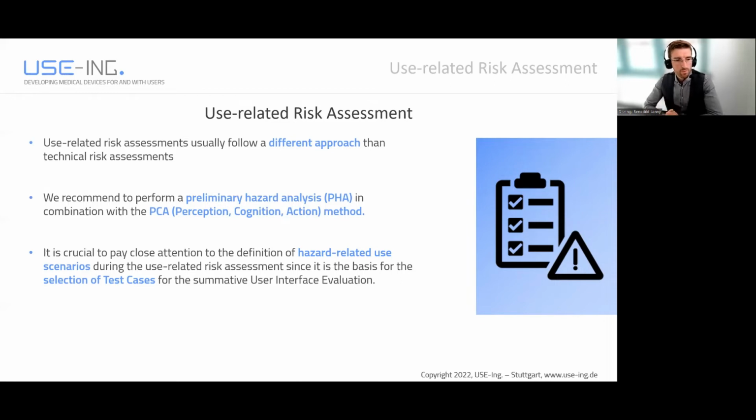It is crucial to pay close attention to the definition of the hazard-related use scenario during the use-related risk assessment, since it is the basis for the selection of test cases for the summative user interface evaluation.